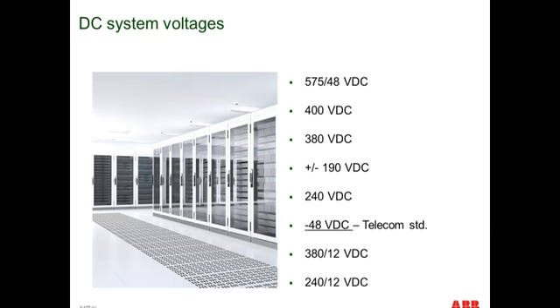We also see 240 volt DC systems being deployed predominantly in Asia and New Zealand. Of course, the industry standard is 48 volt, which is interchangeably used with 53.7. And we see a number of hybrid systems consisting of 380 volt stepping down to 12 volts. You'll also see 380 stepping down to 48 in some instances, and we've seen a number of 240 volt DC to 12 volt systems.